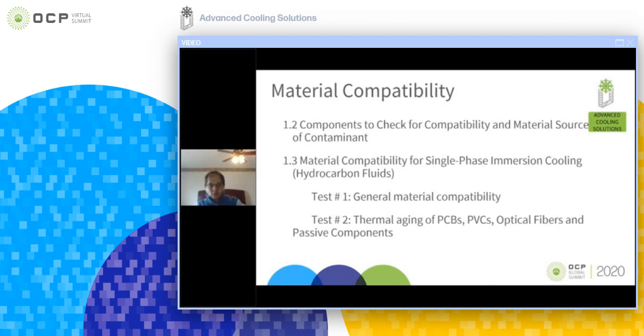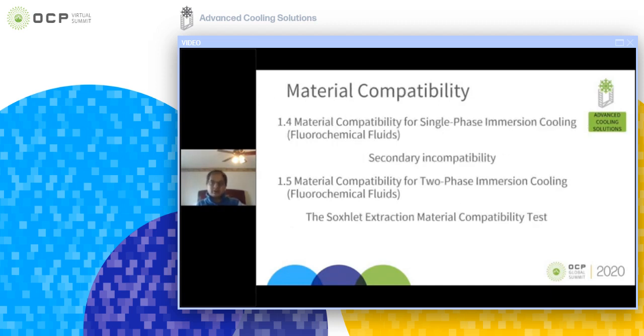Now the material compatibility for fluorochemical fluids is a little bit different. When we talk about fluorochemical fluids for single phase application, most of the materials in the electronics are hydrocarbon polymers, right? The fluorochemicals are so inert that they don't have a direct affinity or reactivity with any of the materials, but you might observe swelling, because one hydrocarbon polymer can release hydrocarbons into the fluid, which are then absorbed by another. This is called secondary incompatibility, where fluorocarbons merely act as a contaminant vector. But in single phase immersion cooling with fluorochemicals, these kinds of incidents are very rare.